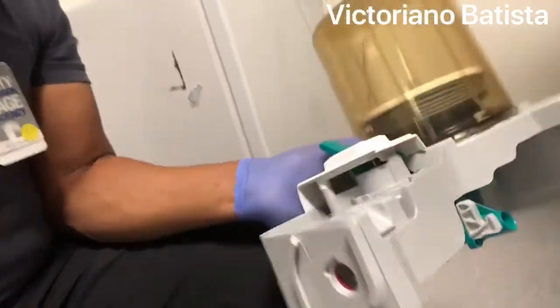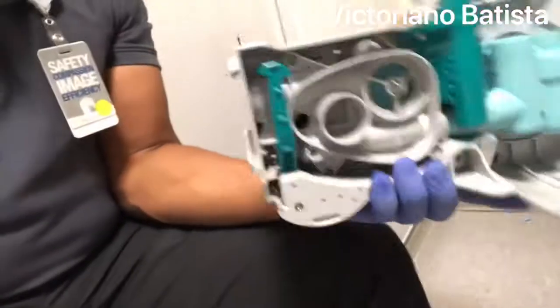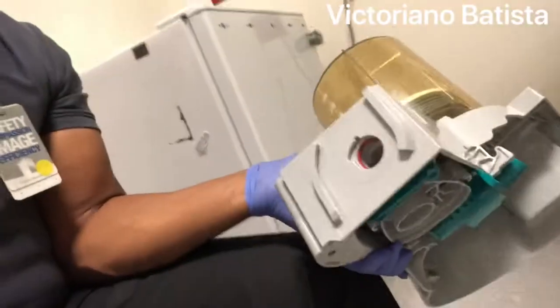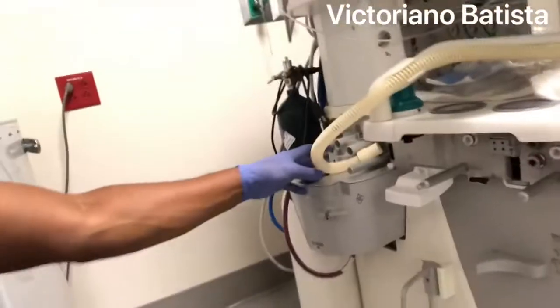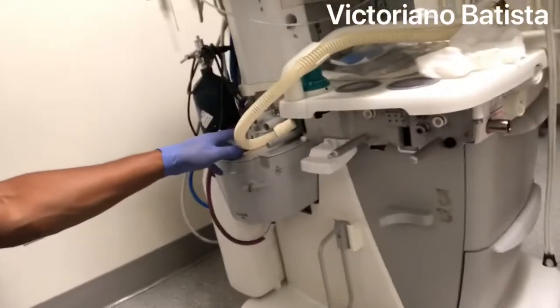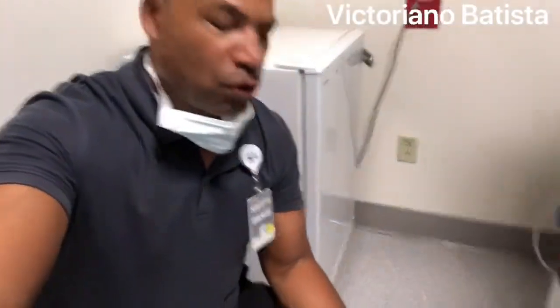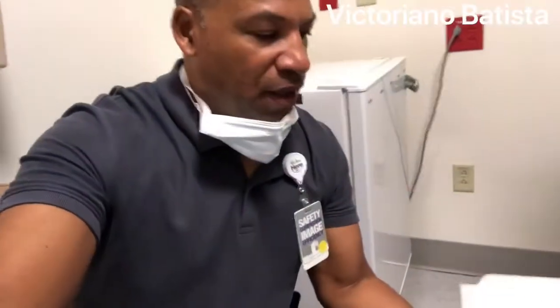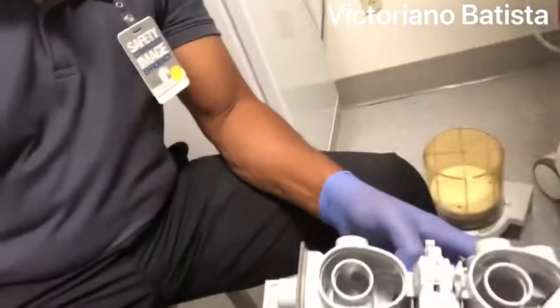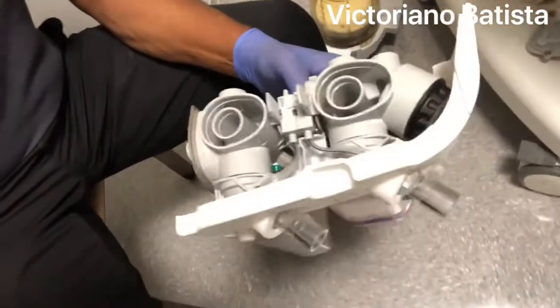So this is the APL valve over here, and this is the bottom of it, and this is where the flow sensors go. And it's pretty much the system here that later on I'll show you how to pull out. It's very simple and it just comes apart, but it's a very good opportunity for troubleshooting and also keeping this unit working as it should.